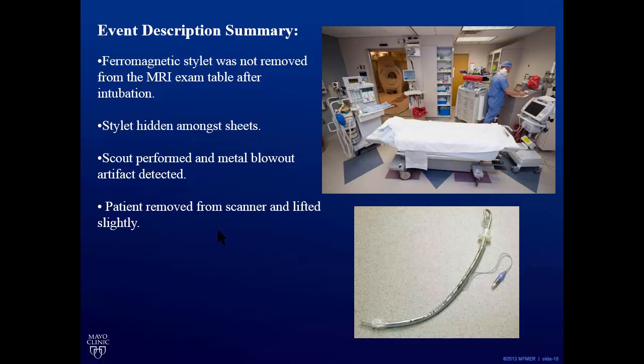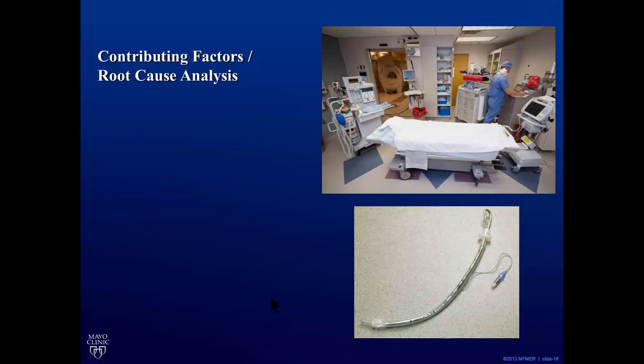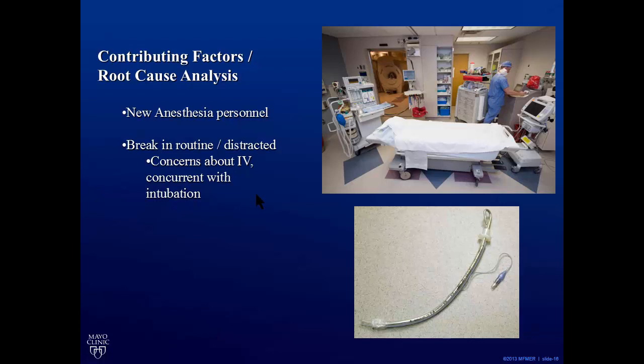The tech went in the room, moved the patient slightly, and then the stylet became a projectile zinging past her ear and flew into the magnet — thankfully not hitting her. There was no injury, but when we did a root cause analysis, there were some new anesthesia personnel in the area that day, and there was a break in routine. They were distracted when they were intubating the patient, there were other folks distracted with a bad IV at the same time, and they just put the stylet down on the bed. We realized there was no organized timeout before entering the MRI to make sure no MRI-unsafe materials were still around.